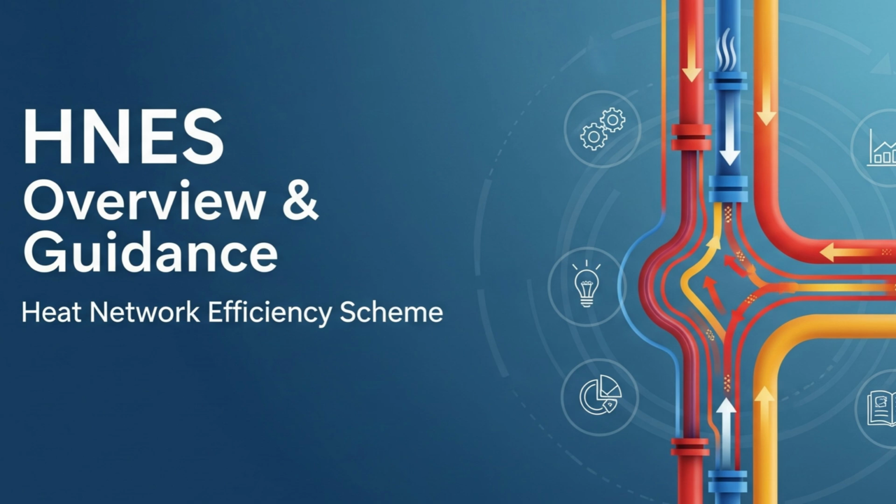Totally. But their existing heat networks were, frankly, degrading. They were inefficient and they suffered from poor metering, so they didn't really know where the heat was going, and aging, failing insulation on the pipework. The HNES intervention here was crucial. The scheme provided over £250,000 in capital grants spread across 2 separate applications.